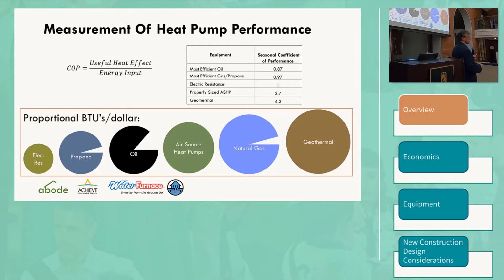A heat pump, especially a geothermal heat pump, the energy you put in is being used to harvest energy from the ground during the heating cycle. Because your only overhead is the harvesting of that heat, you always end up with more heat put into the structure than energy you put into the system. So our COPs are always a lot larger than 1.